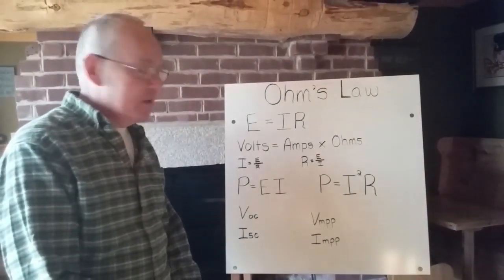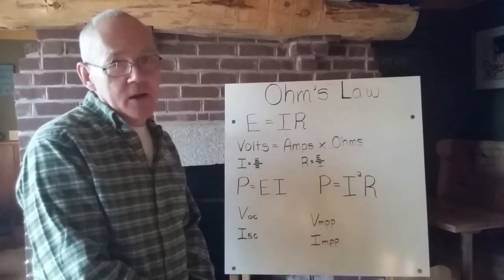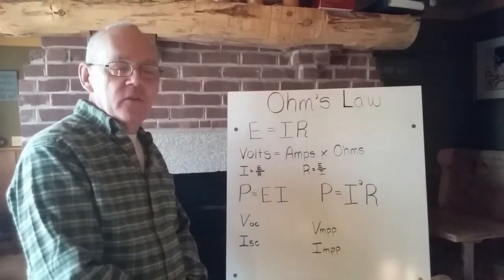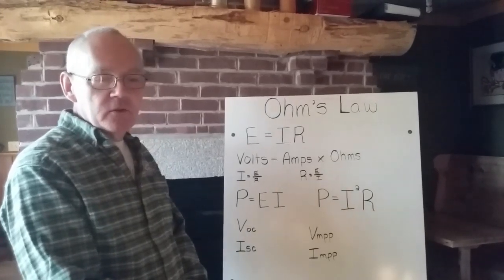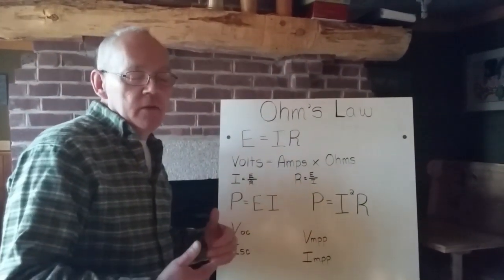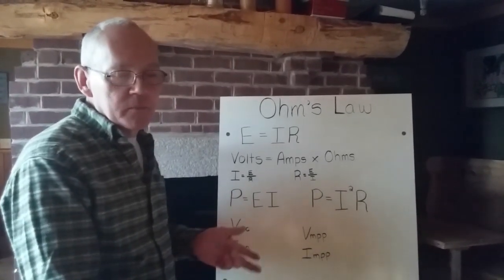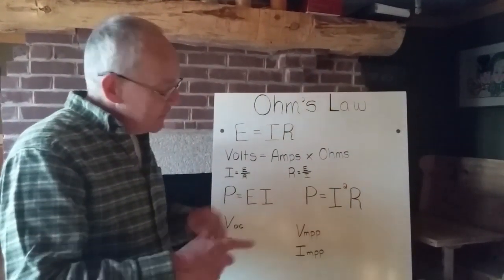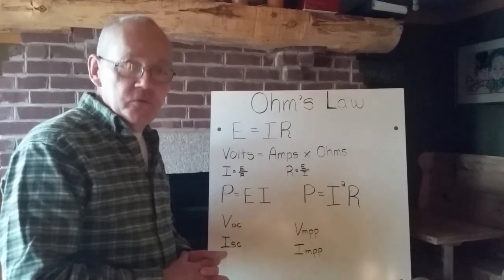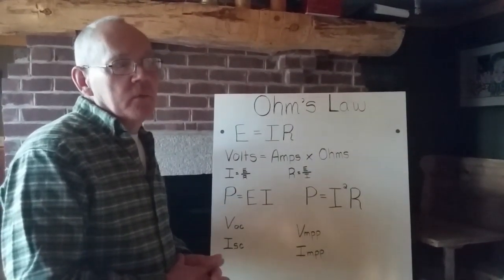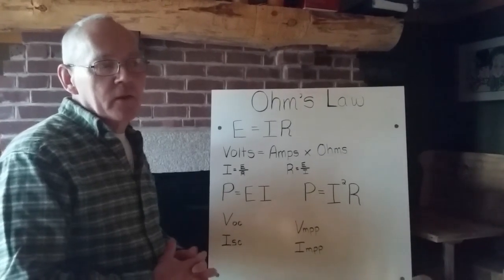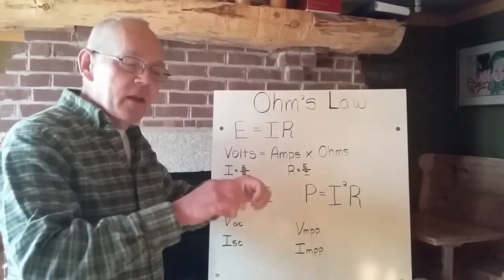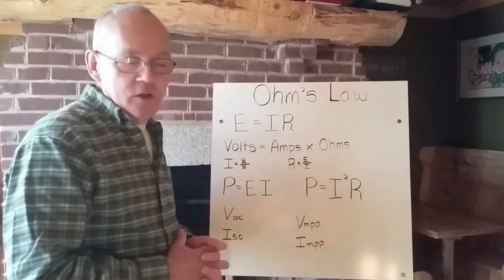But it gets even more complicated than that because the maximum power point moves around. It depends on just how sunny it is. It's in one place under the test conditions. That maximum power point is going to be in a different place at different voltage, different current when it's partly cloudy and it's going to be in yet a different place when it's really cloudy and all over the place in between those extremes. And this is what a maximum power point controller does for you. It measures the amount of voltage and current coming from your panel and adjusts them to put it back on the maximum power point and bring every last watt out of the sunshine that it can.